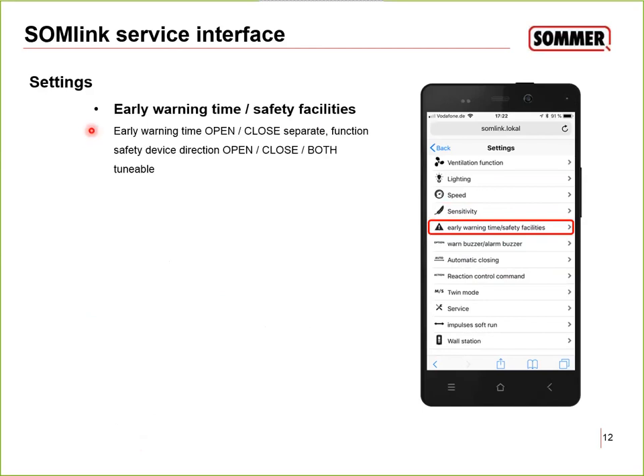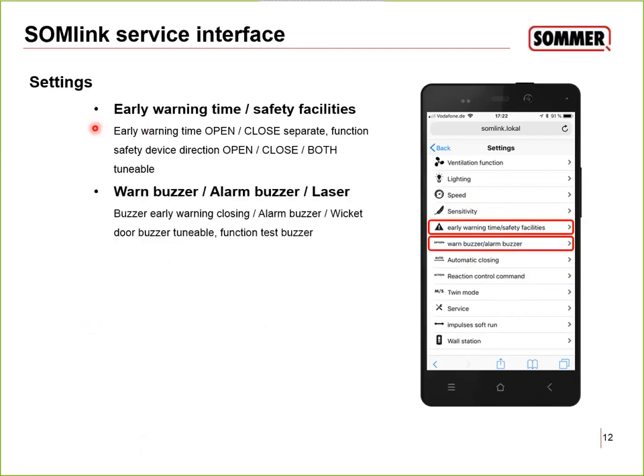Next is the early warning time. If you have a warning light connected, for example, and you want a pre-warning before the operator starts, you can set the time here, also separately for door open, door close, or both directions. However, if there is a warning buzzer, an alarm buzzer, or a laser connected, there are several setups possible at this position.